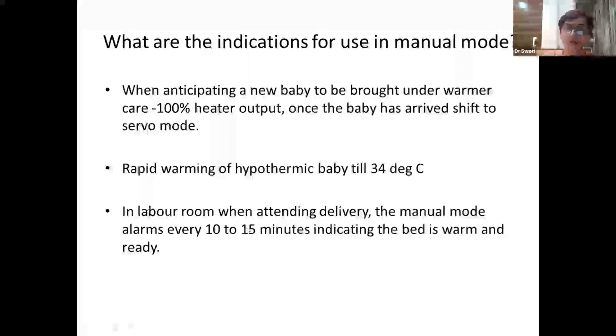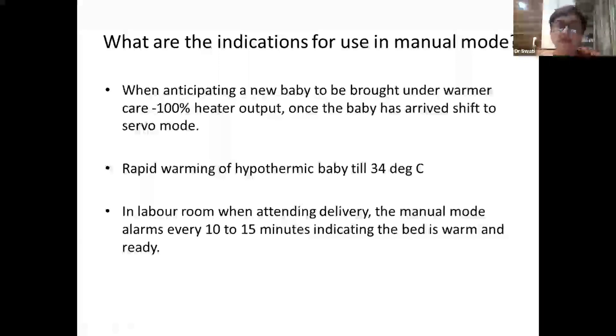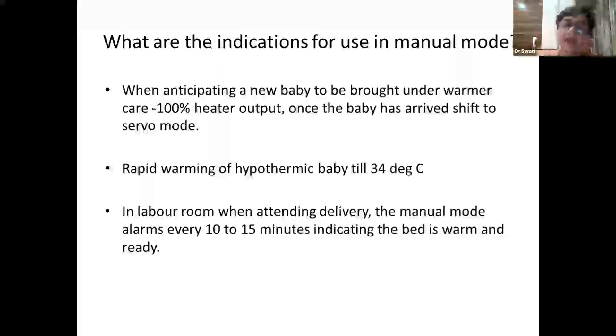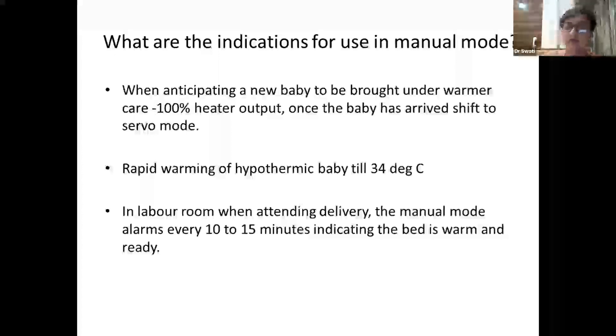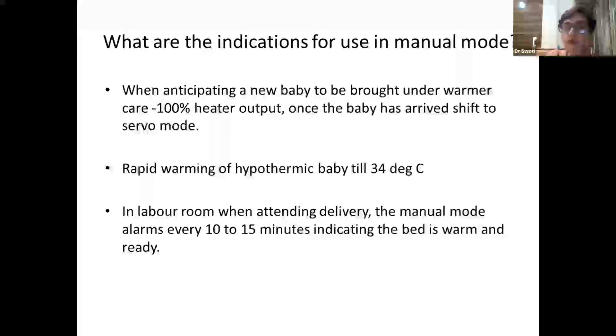Beyond 34 degrees Celsius, only slow re-warming is performed — not rapid re-warming. In the labor room before a delivery, the manual mode can be kept on; it will alarm every 10 to 15 minutes indicating the bed is warm and ready to use.